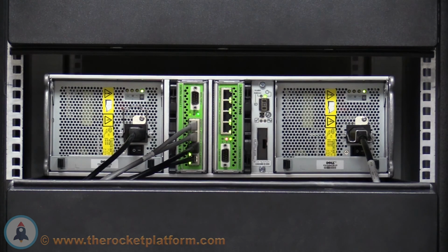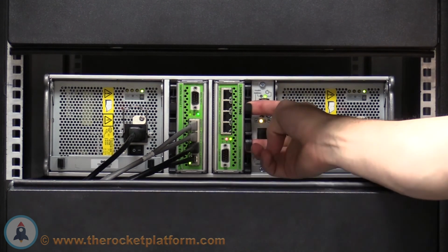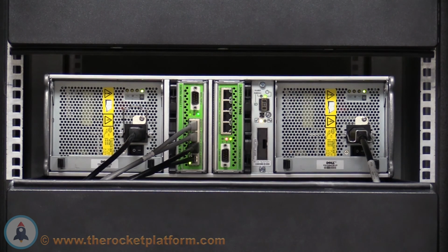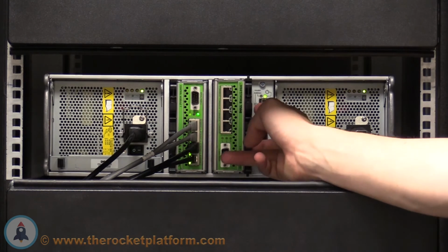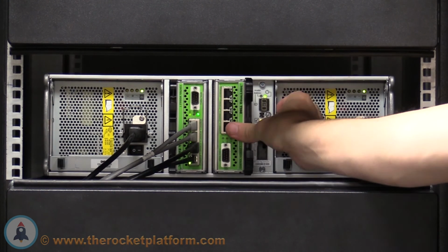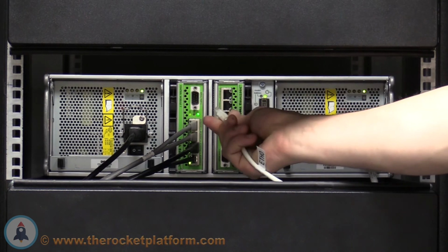Grab on one of the levers, making sure not to disturb the tab attached, and pull straight back. If the controller stays in place, then it has been properly seated. If the controller moves around in the slot, then you must reseat the controller until properly seated. Attach the cables according to how you labeled them.